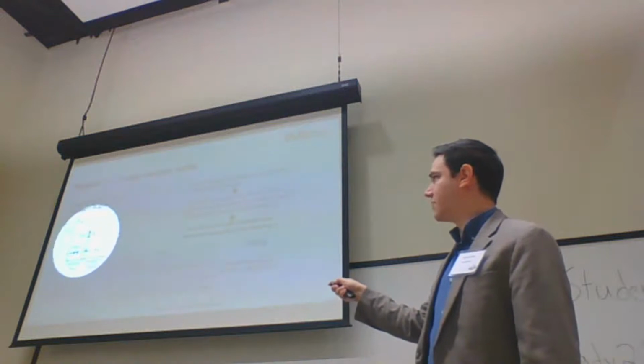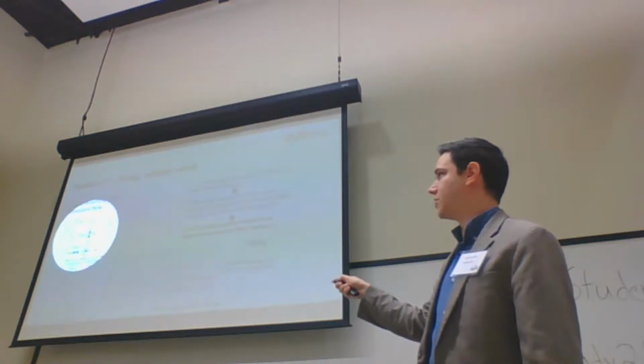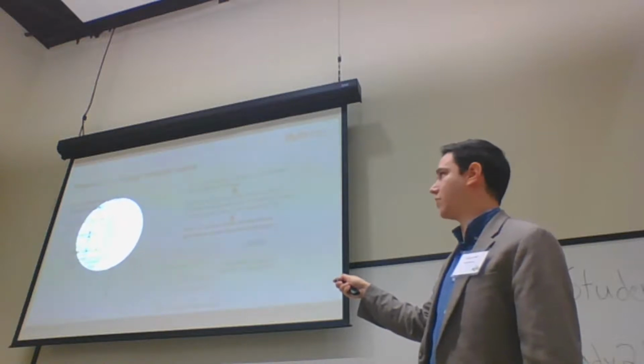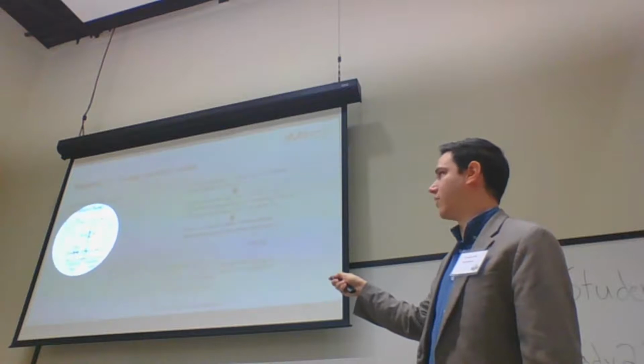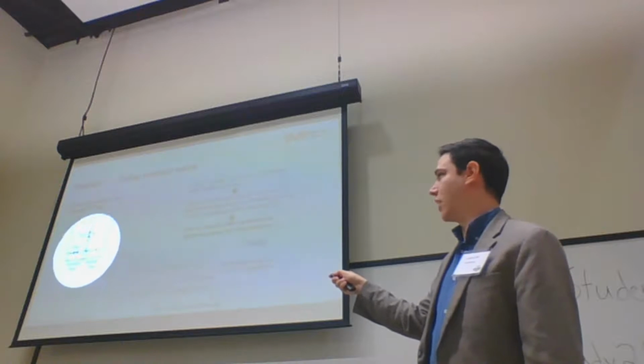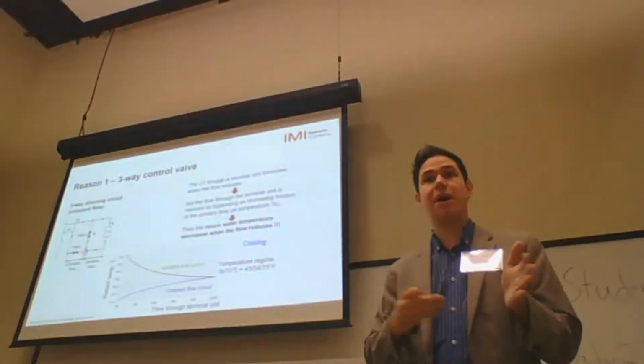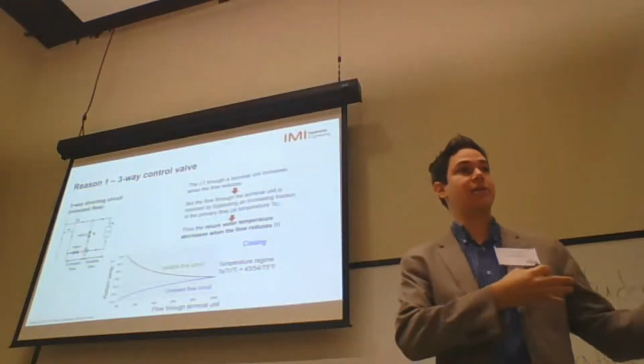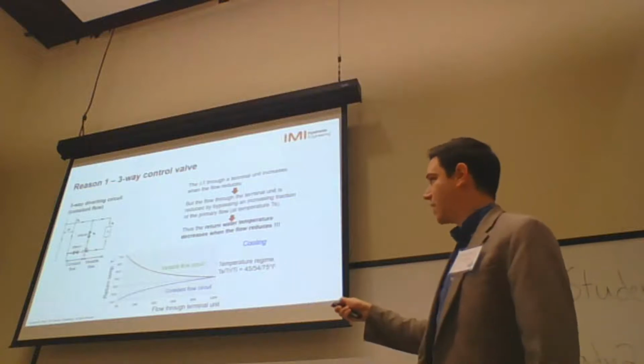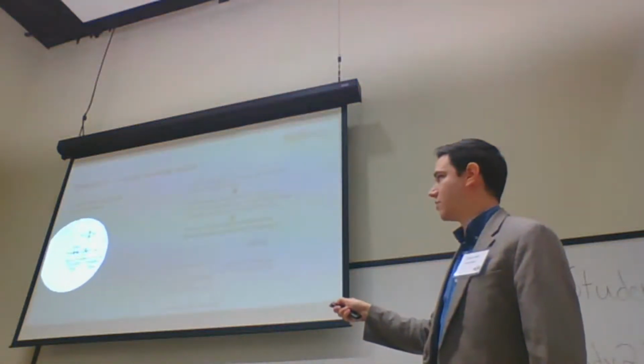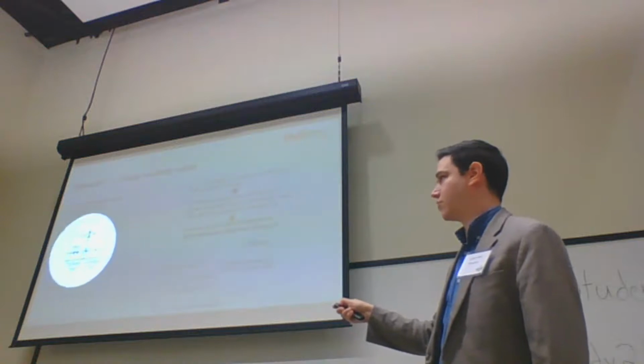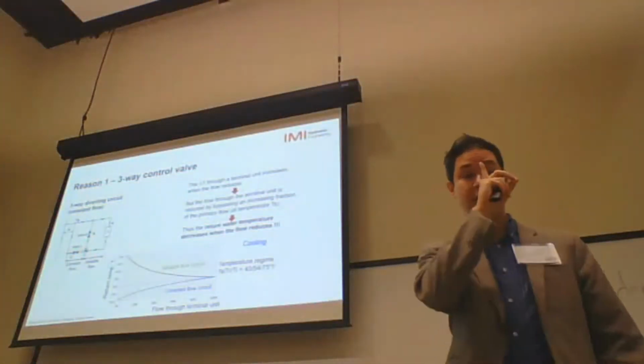The reason that I have these two balancing valves right here, this balancing valve on the bypass, is to match exactly the pressure drop of the coil. So if you have a coil with a 3 psi pressure drop, this balancing valve right here is going to match the same 3 psi pressure drop. So when my modulating control valve or my on-off control valve is changing flow between bypass and coil, it's not affecting the whole balancing in the rest of the installation. And this other balancing valve is just to equalize the pressure drop between the other units. So just to balance like a normal balancing valve in the system.